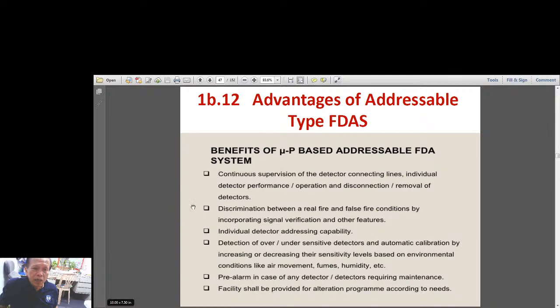Okay, and the benefits of the addressable type FDAS are mentioned in here: continuous supervision of the devices, discrimination between a false fire and a real fire, individual detector addressing or communicating capability, detection of over and under sensitive detectors, and pre-alarm in case of any detector failure. Meaning to say, if one detector is defective, then it can raise an alarm. While in the conventional, you will never be able to know it until you do an actual test and it's not functioning. And facility shall be provided for an alteration program, so it can easily be maintained, because the CPU, the central processing unit, or the computer, can be made to communicate with the different components in the system.